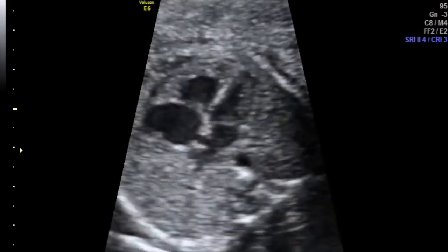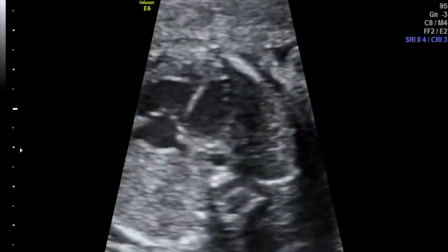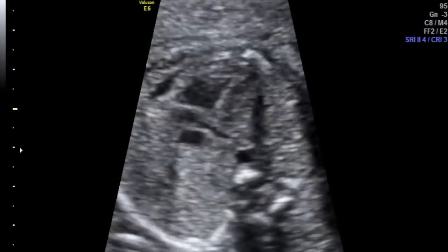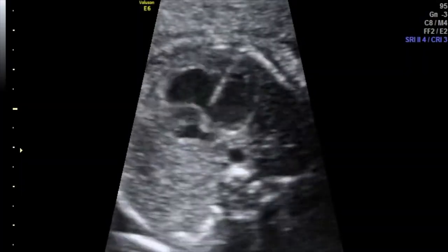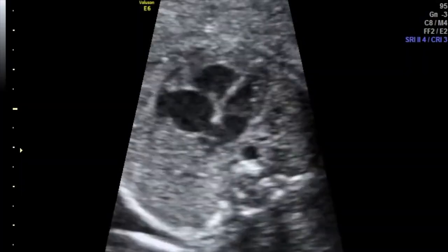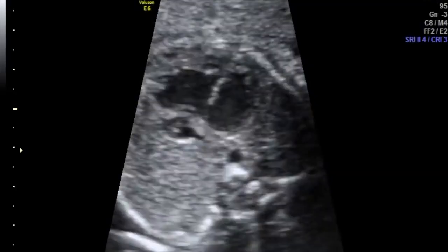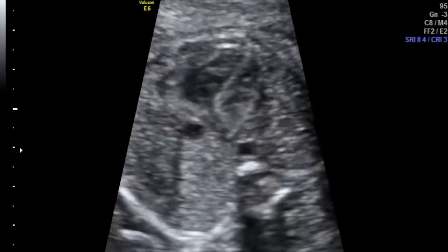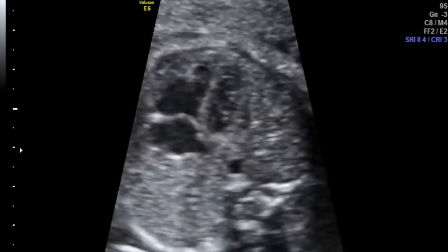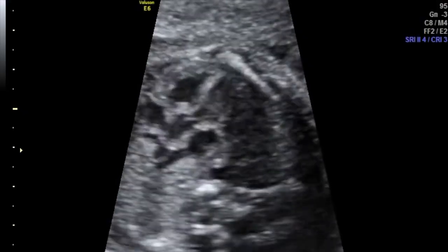One very important tip is that whenever you are analyzing the fetal heart, always use cardiac presets. All the machines nowadays have presets which are fixed for particular scans, and you should tell your application specialist to make particular cardiac presets in your obstetric settings.